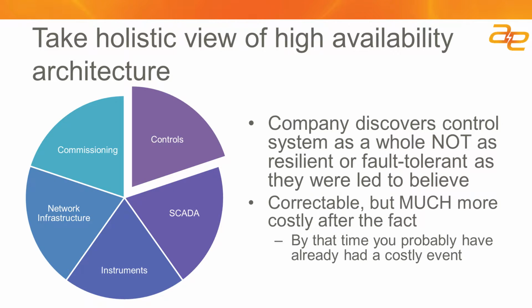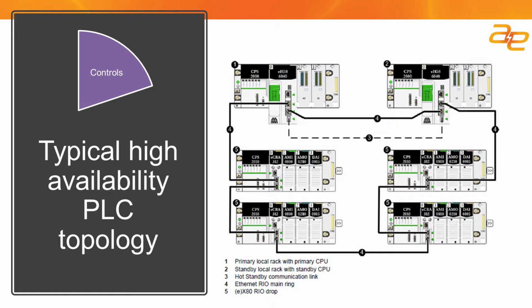Up to now, we've primarily talked about the controls portion of a facility or of a system. But the controls only make up a portion of the overall system. So let's talk a little bit about each of the different components that might make up a control system within a facility. The first is obviously the controller itself, or the programmable logic controller, PLC. As you can see, I've presented a typical topology. This is an example that I took from a recent Schneider Electric instruction manual on building a redundant architecture, and this is typical of other manufacturers such as General Electric, Allen Bradley, as well as Siemens.